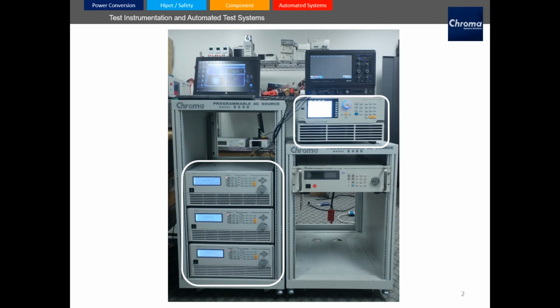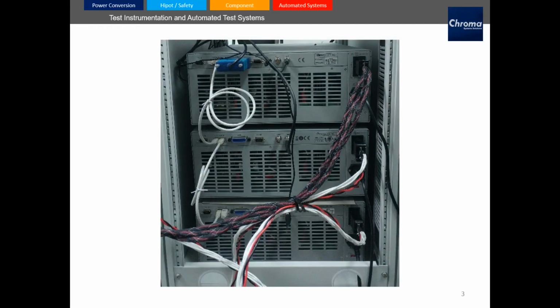To use these units in master-slave mode, we use the provided system bus cables and terminal resistors. These cables supply a sync signal to coordinate turn-on and turn-off, as well as load changes, in order to prevent the loads from becoming desynchronized.